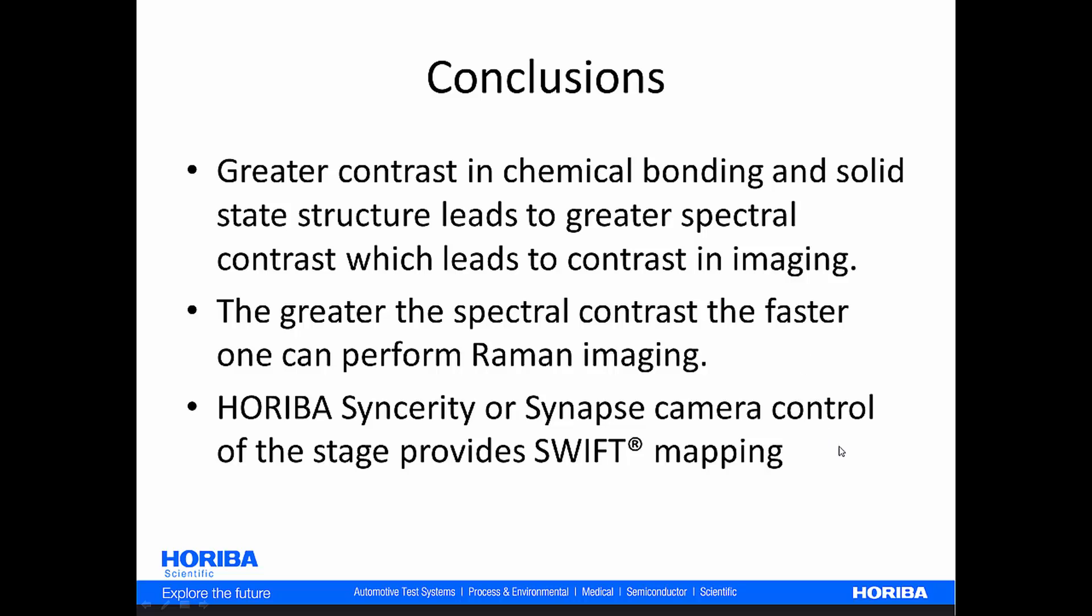And finally, the use of SWIFT mapping wherein the Syncerity or the Synapse camera is controlling stage movement and is communicating with the stage such that you have constant stage motion and timing of the camera with the stage motion with the shutter always open, gives you a real significant improvement in your speed for fast Raman imaging.